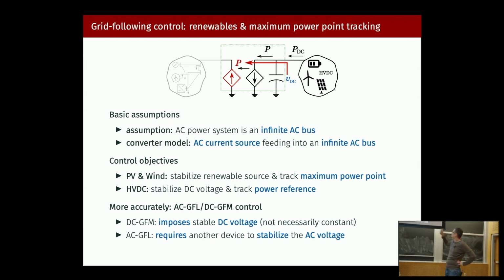These things are typically called grid following control. I want to put a bit of a twist on this: it's following the AC grid, but it's actually forming the DC grid. If you look at things like high voltage DC transmission, these typically stabilize the DC voltage, and then you have a DC grid behind it. So they're actually grid forming on the terminal that, from the viewpoint of an AC system, you wouldn't really care about. But the bottom line is this is relatively fragile because you need someone else to stabilize your AC system. That's the problem.